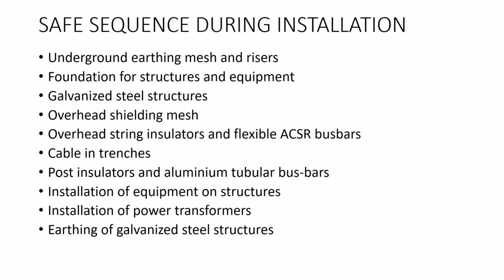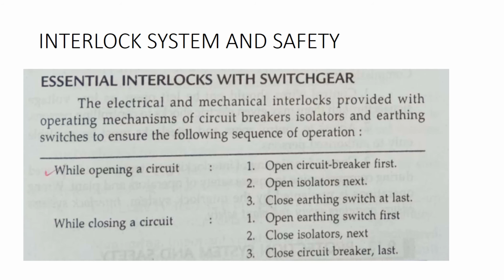In this above sequence, the overhead work is completed before commencing the installation of equipment on the ground. While overhead shielding mesh and flexible buses are being erected, work on the ground level is avoided. And the next point is interlock system for safety. Now, suppose we are operating something, we have to keep some interlock mechanisms. Otherwise, if interlock is not there, sometimes we will be in trouble.